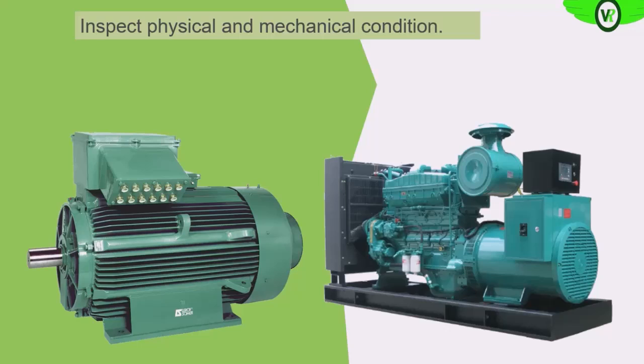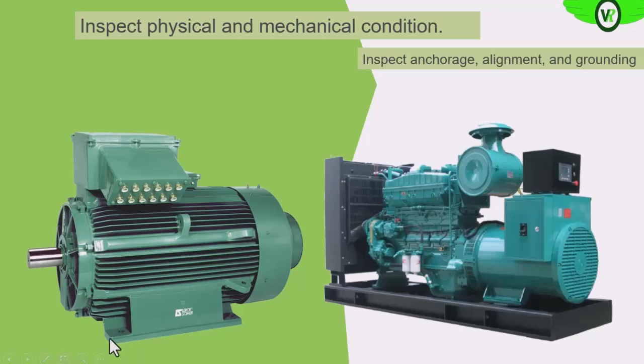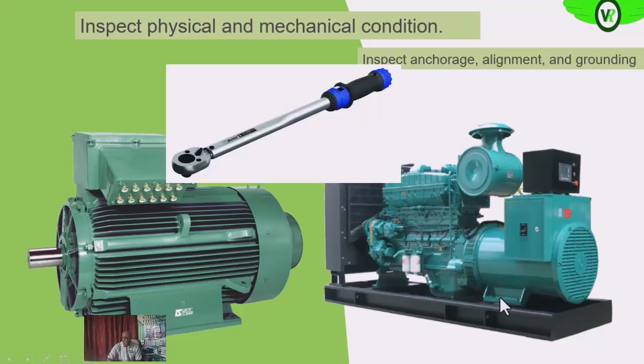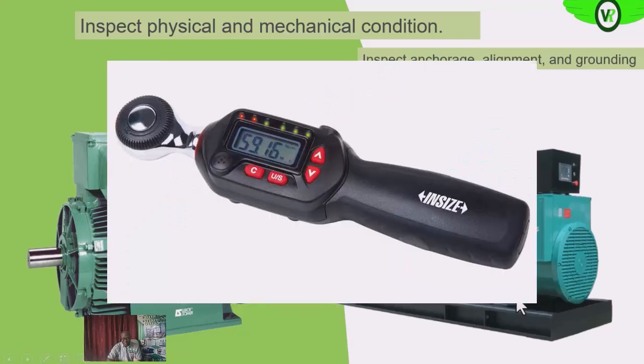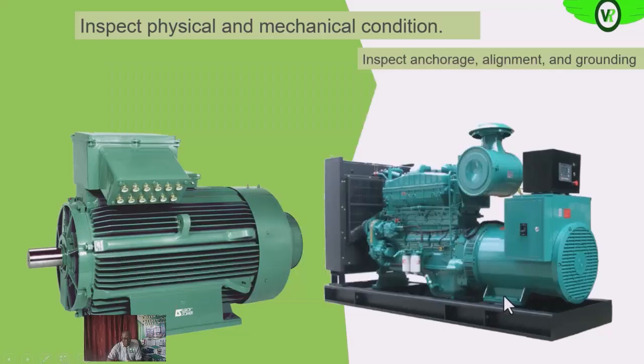So you also carry out other physical inspection. You look at the frame to see that it is clean. The anchorage, the hold down bolts, you also check the hold down bolts on the electric motors and the alternators to see that they are firm. You can even torque them to ascertain that they are up to the specified torque level with your calibrated torque wrench. Okay, so you check to see that they are firm.